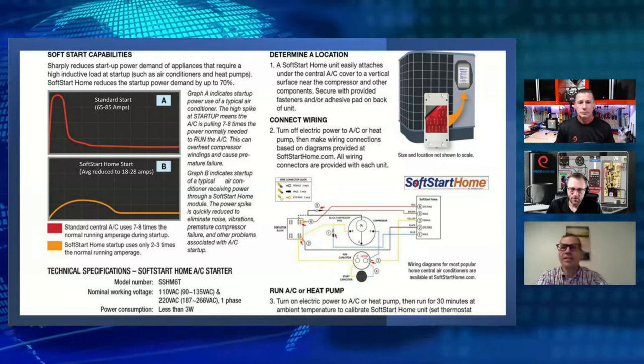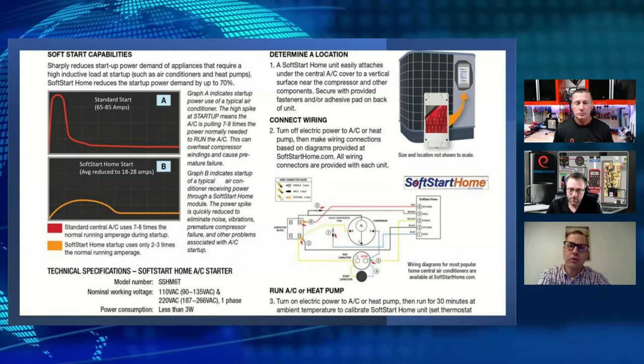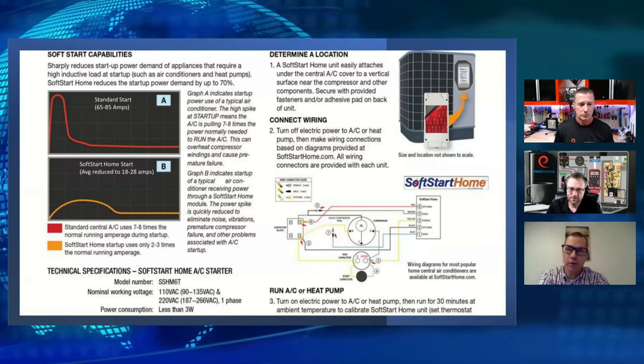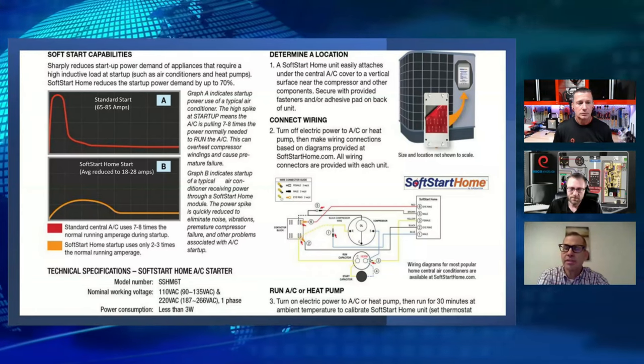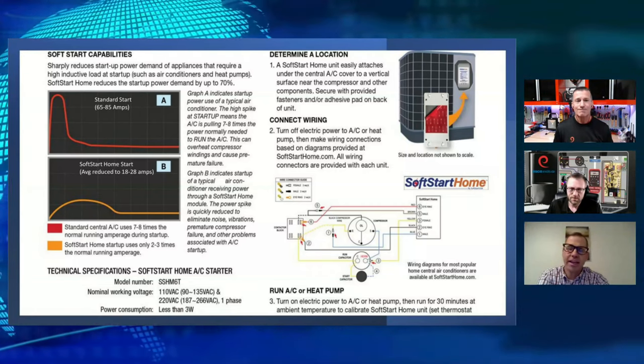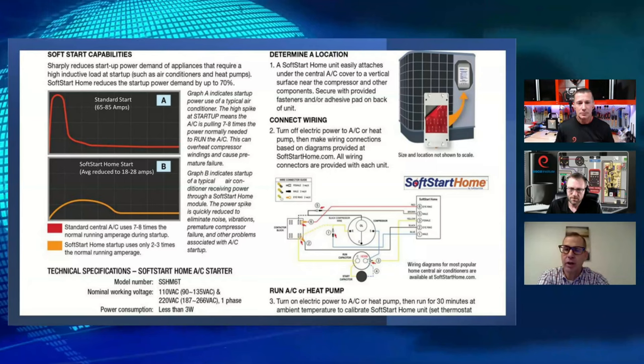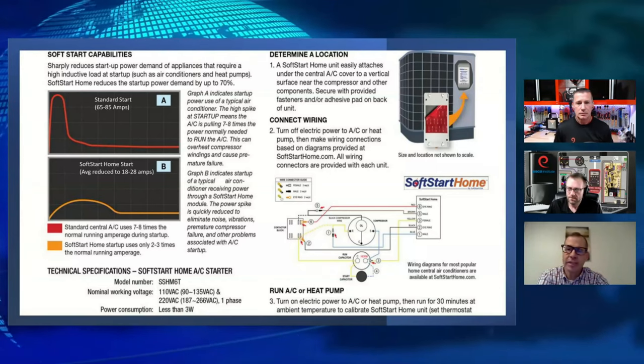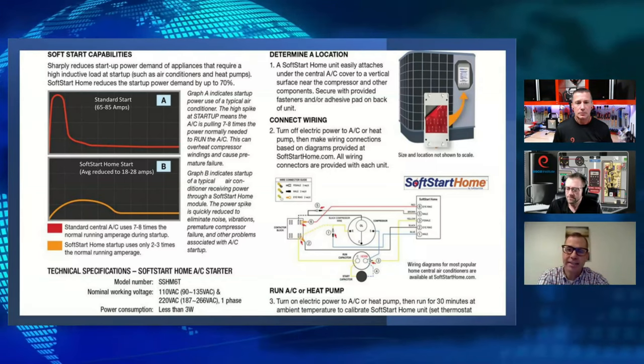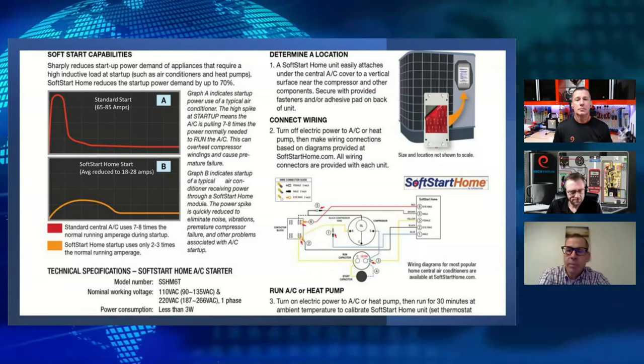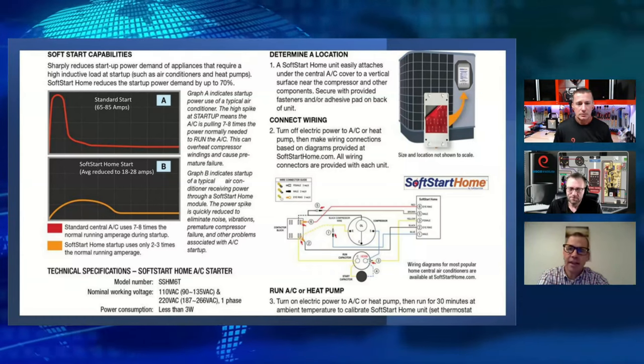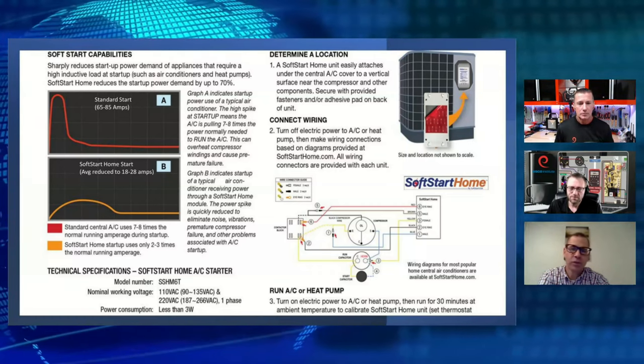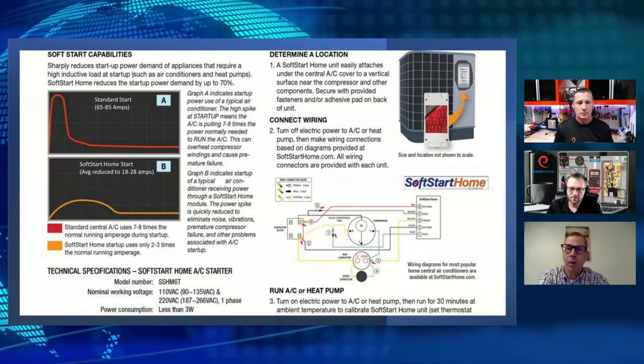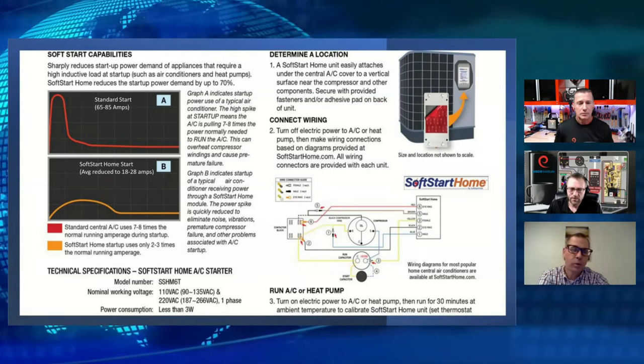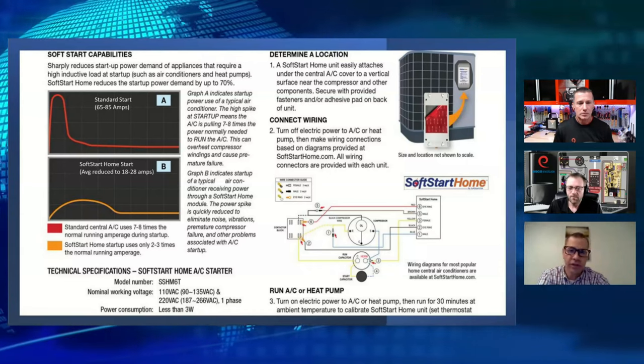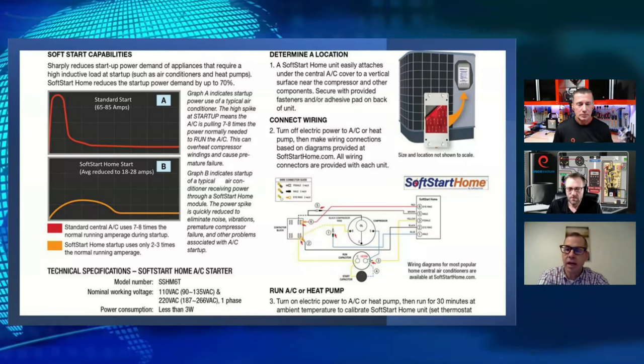This slide shows, much like your own personal experience, standard startups can be 65 to 85 amps. After putting on the soft start, we've seen an average reduction down to between 18 and 28 amps — a big difference in that inrush of amps, and what that can do for compressor longevity over time.